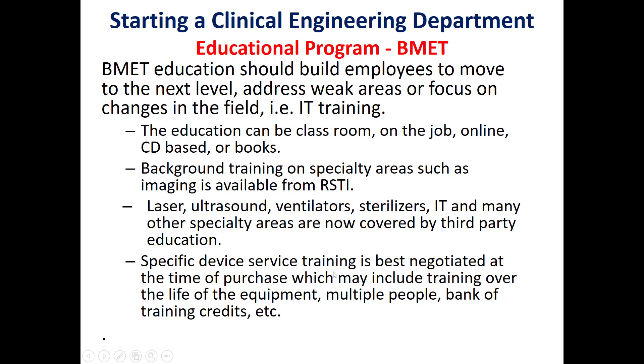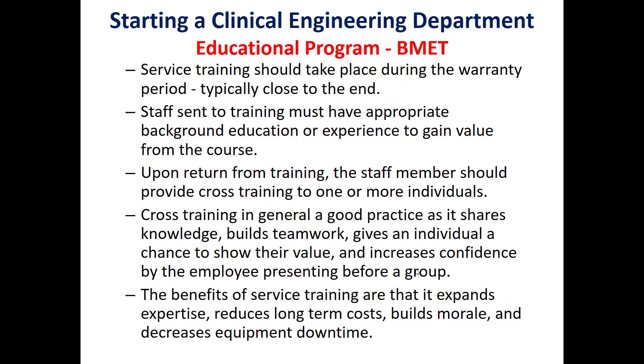Specific device service training is best negotiated at the purchase phase, so during purchasing we should negotiate this part. The service training should be done during the warranty period and preferably near or close to the end of the warranty period.